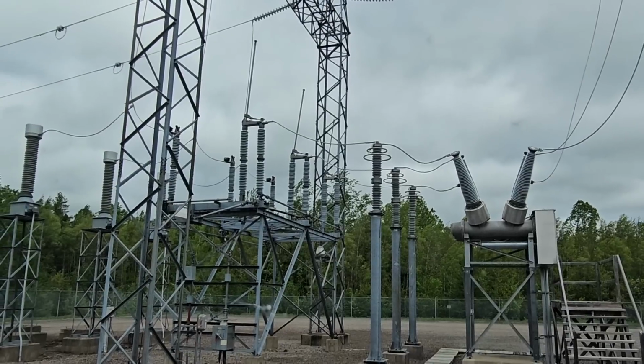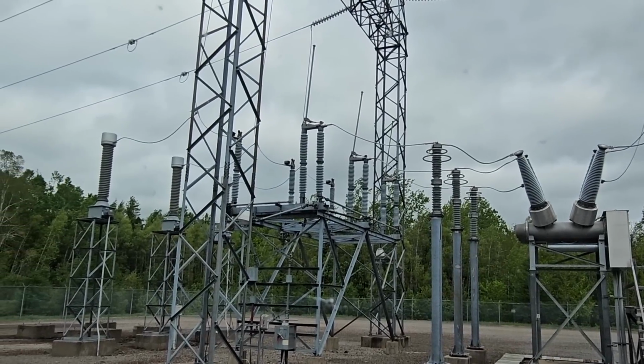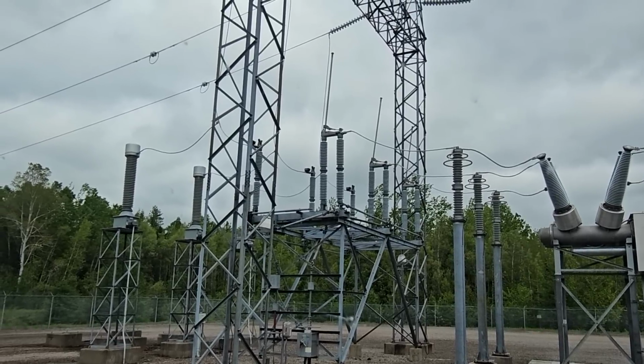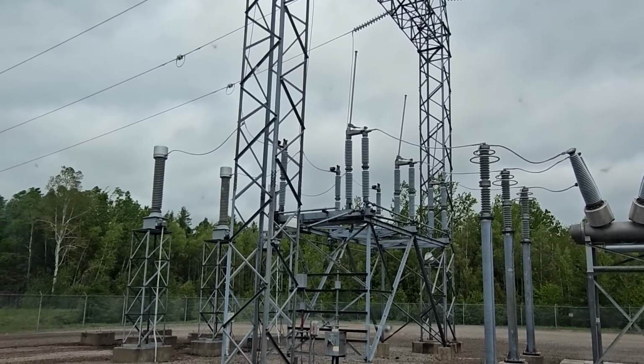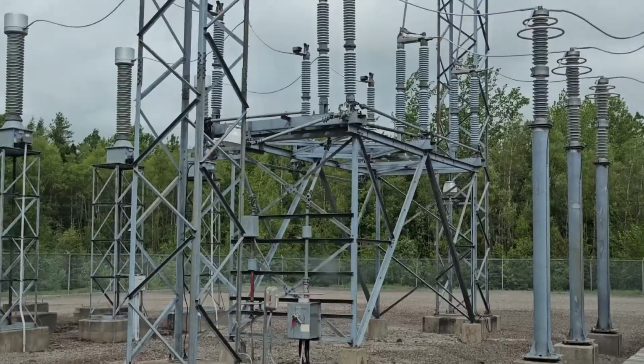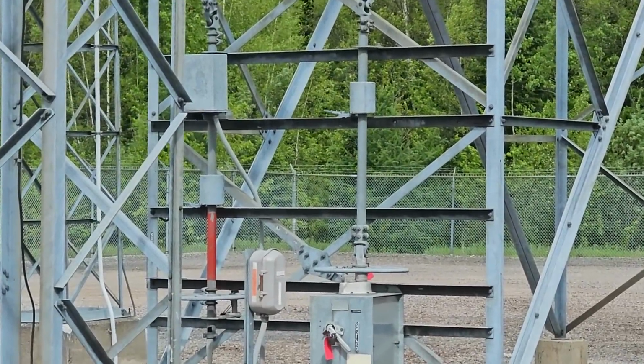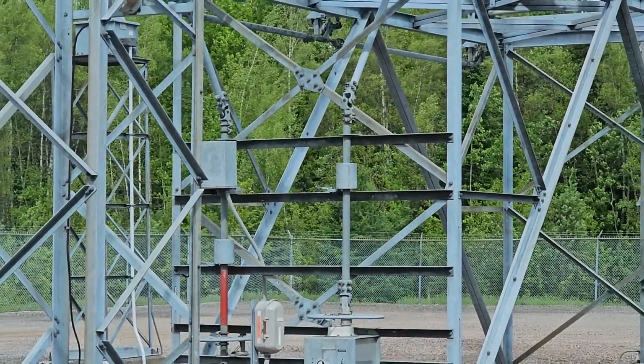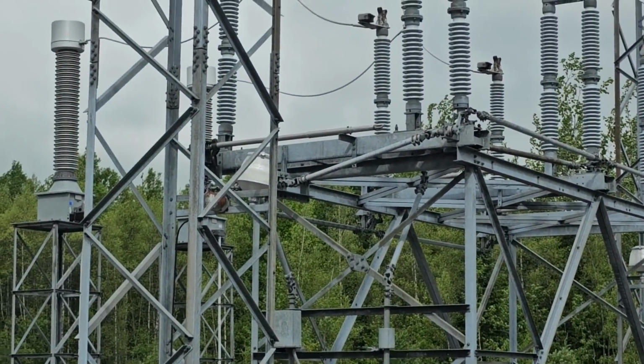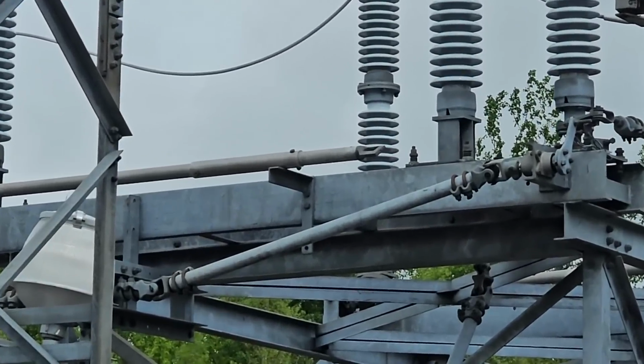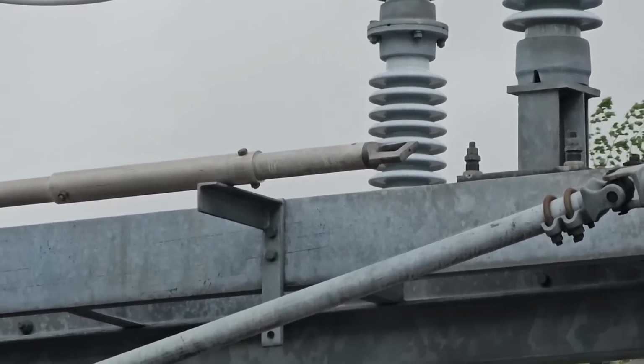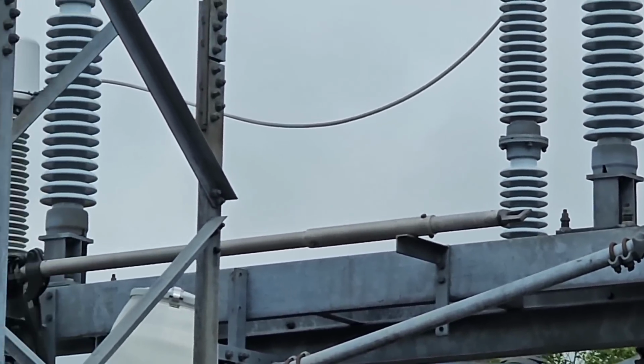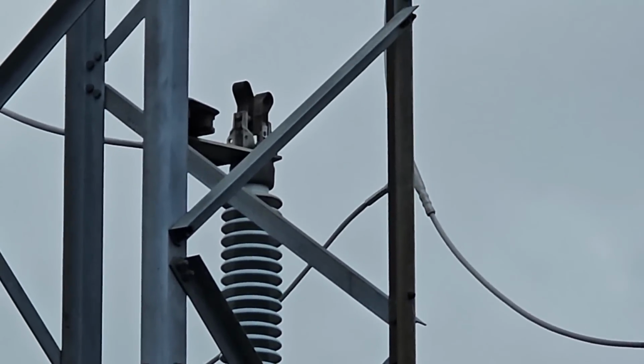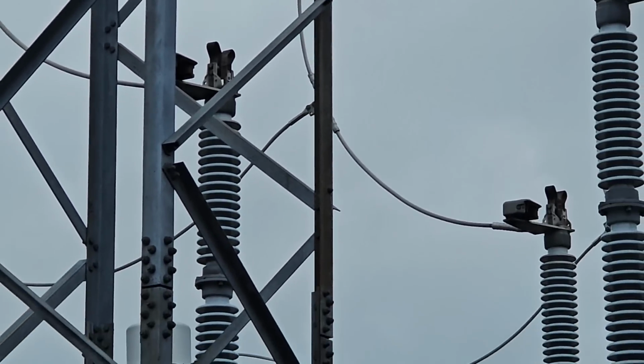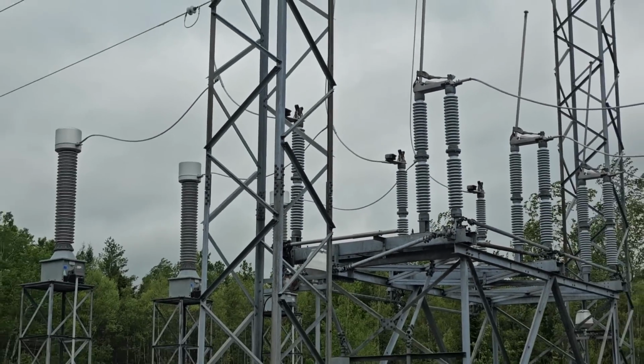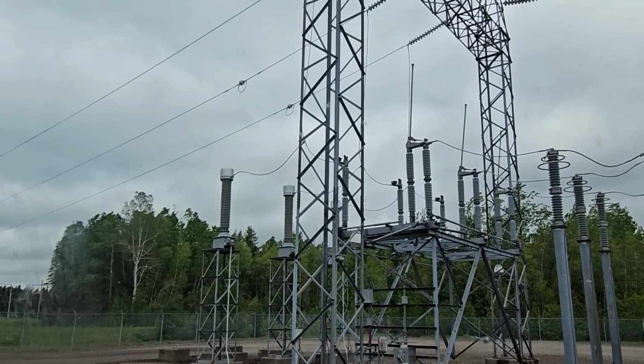So just the last step, I'm waiting for the terminal that's probably about a 2-hour drive from here. The guy's got to do the same thing on his end. And then my last step, I'm going to close the ground switch. All of our ground switches are painted red, that red handle there. It's basically like putting 3 grounds on, but instead of putting 3 grounds on, there's a drive pipe. You see this pipe right here that's laying flat? That's actually going to flip up and slide right into that connection up top. So that's tied to ground. That's going to be a trip ground for that 230 kV line.